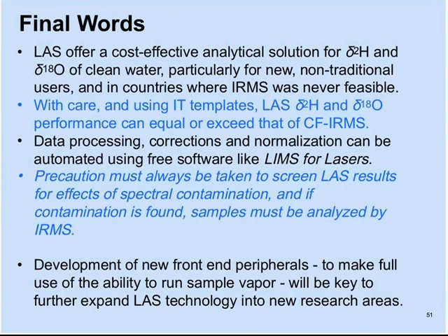Okay, just to finish up, as mentioned before, the lasers are a cost-effective solution for waters. And using great care and templates, I think you can find that your laser will perform equal to or exceed that of certainly continuous flow instruments, and we're getting there for 18. Data processing can be made easier using LIMS for Lasers software. But again, precautions should be taken that you screen your results for spectral contamination. One of the outstanding things still is areas of development are needed for front-end peripherals to make full advantage of the water vapor, for example, and those are areas that hopefully would go into the future.